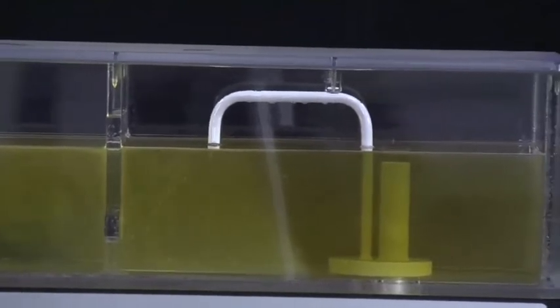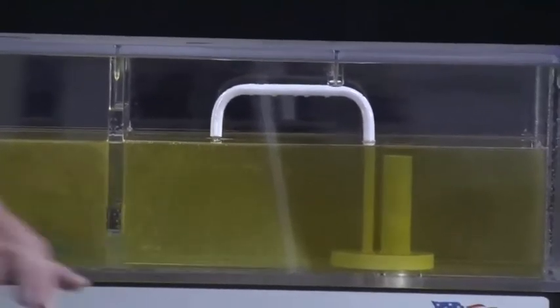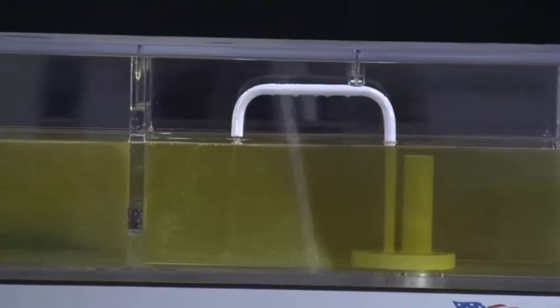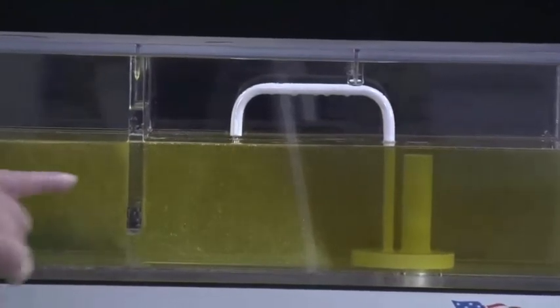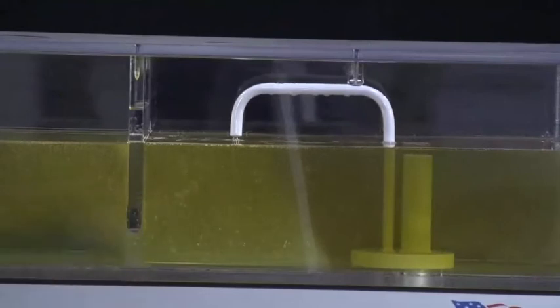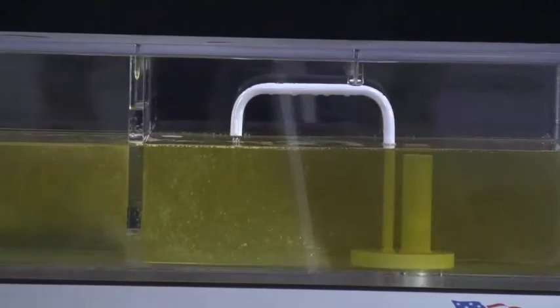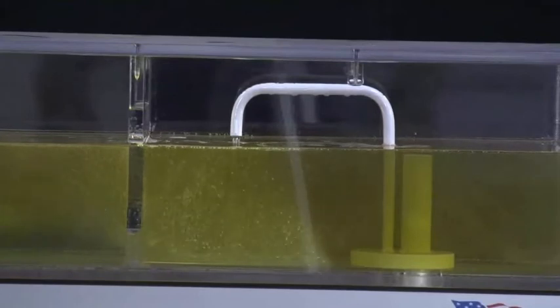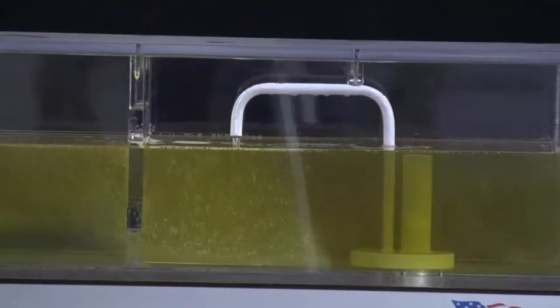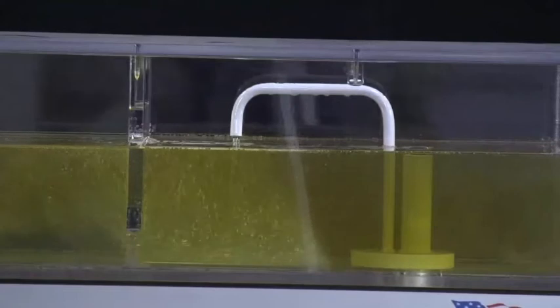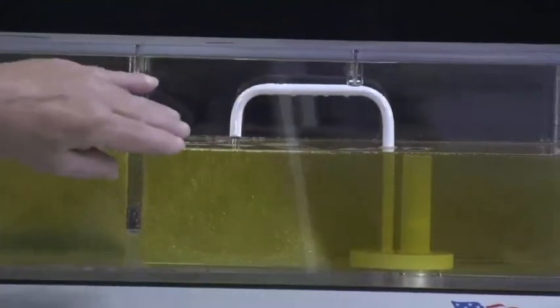All right, so now we're just about out of the oil. I'm now dropping 1.8 gallons a minute in on top of the oil in the reservoir, and you can see the amount of turbulence it's generating within my reservoir, and that is going to generate air, which is back to, as we said, pseudo-cavitation. It's starting to aerate the oil.